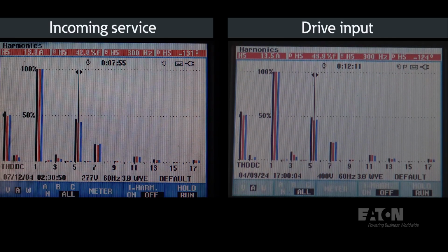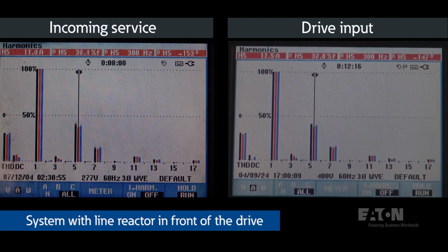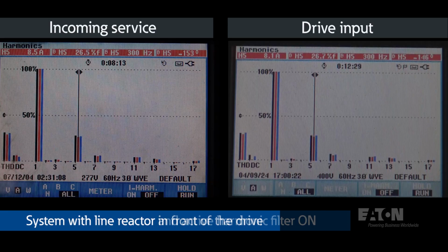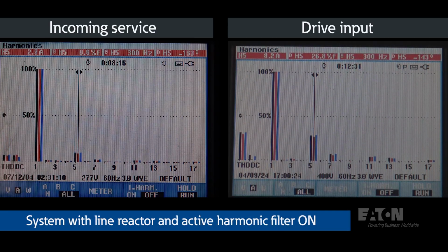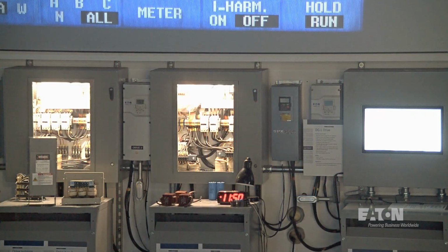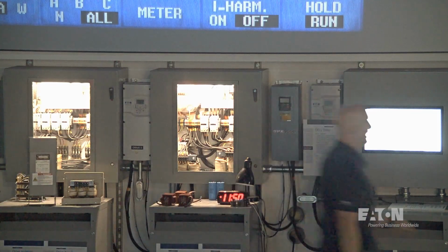And the next thing I'm going to do is add in a line reactor in front of the drive and show that with that it dropped down the fifth harmonic current to about 8.6 amps. And now I'm going to turn on the active harmonic filter, and with that additional larger reactor, of course, the incoming looks good, but the input to the drive looks almost the same. So let's talk about that for a minute and see why that actually happened.